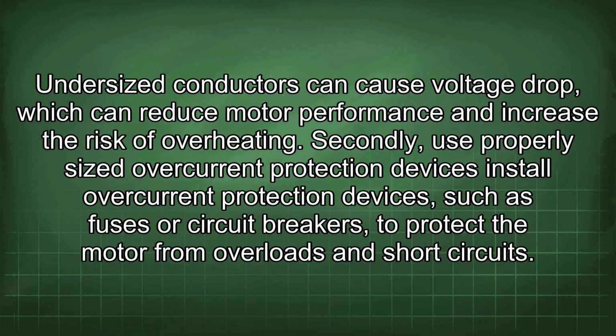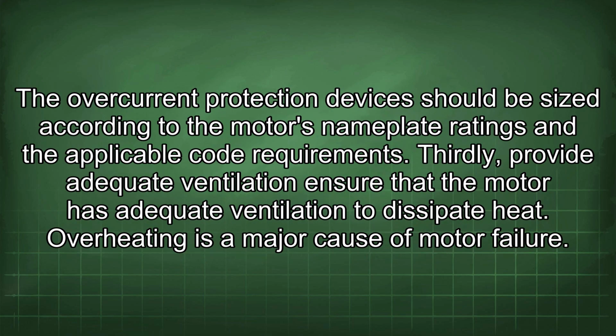Secondly, use properly sized overcurrent protection devices. Install overcurrent protection devices, such as fuses or circuit breakers, to protect the motor from overloads and short circuits. The overcurrent protection devices should be sized according to the motor's nameplate ratings and the applicable code requirements.